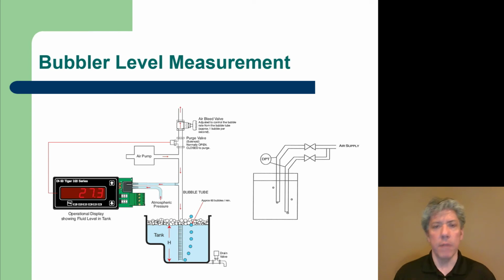Now, the density of the fluid makes a difference in the reading, because from fluid statics, the density of the fluid rho is in the equation for relating the pressure at the bottom of the liquid to the height of that liquid column. And so there's another method that can be used for measuring the level in fluids if you have two or dual bubbler tubes. Now you notice there's an air supply off to the right that is pushing air through both of these tubes. There would be similar setups of bleed valves and purge valves for each of these, but let's concentrate on the bubbler tubes for the moment. The ends of the bubbler tubes are at a known height difference in the fluid.